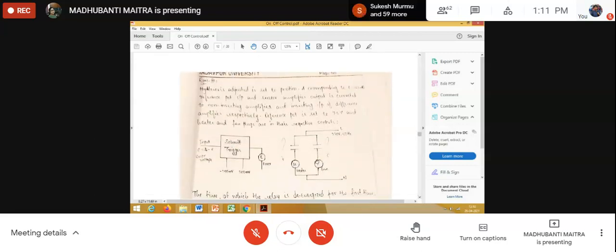But this circuit is incorrect. Heater and fan are connected to the supply through these two contacts, but both the contacts cannot be normally open, right? So this is the symbol for a normally open contact, and if I cross the normally open contact in this manner, then that particular notation is used to represent a normally closed contact.